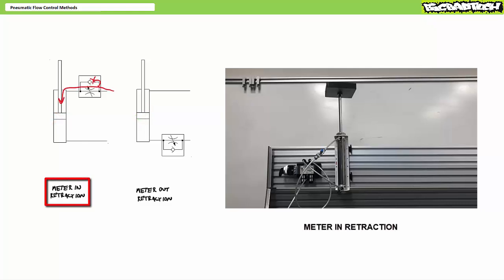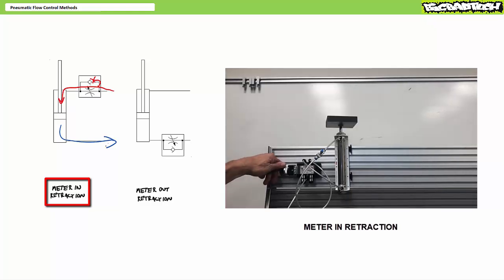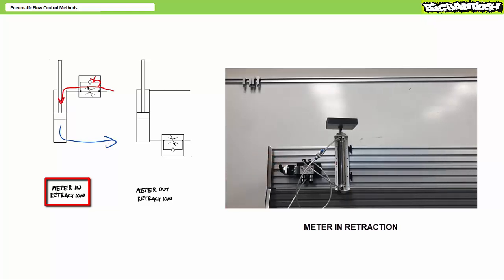A meter in retraction does control flow entering the rod end. However with no restriction on the cap end, as soon as the cap end is exhausted to atmosphere, the load slams to the ground. Not exactly the best load handling system if you wanted to keep the load in any usable state.